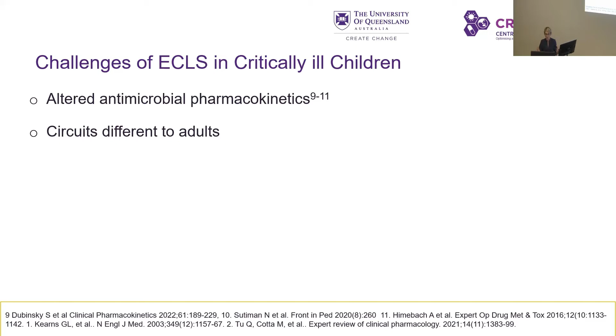The priming volume relative to the child is very different. So a neonate might have a volume of about 250 mils if they're about 2, whereas you might prime the circuit with about 370, equating that it's 600 plus mils, which is nearly 3 times their actual total circulating fluid. So we're dosing that. What are we actually dosing them for? We're dosing them for the fluid volume, or what are we actually doing?